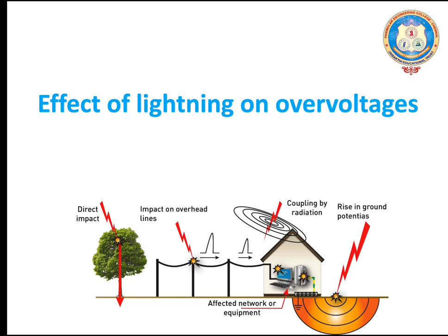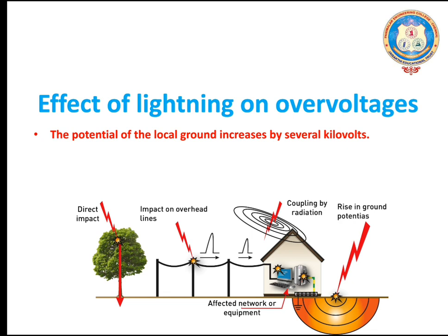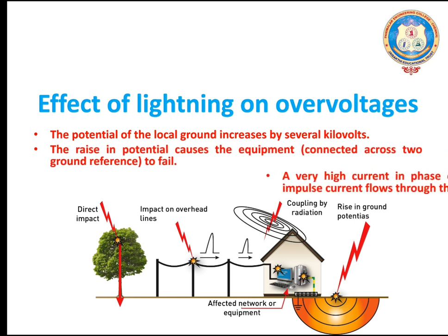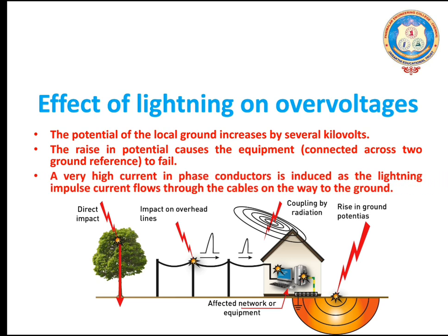What are the effects of lightning on over-voltages? The potential of the local ground increases by several kilovolts. The rise in potential causes the equipment frame connected across the two ground references to be stressed. A very high current in the phase conductor is induced as the lightning impulse current flows through the cables on the way to the ground.